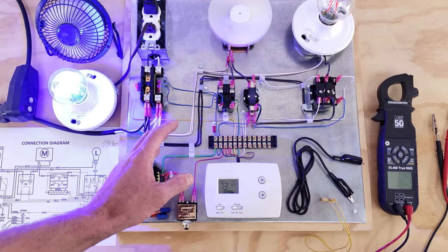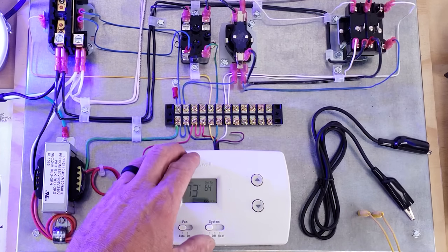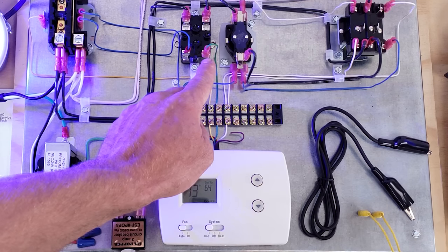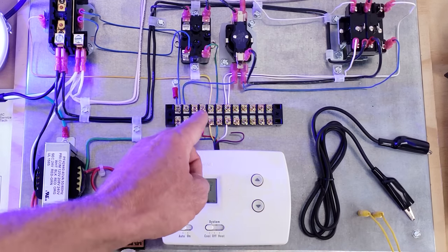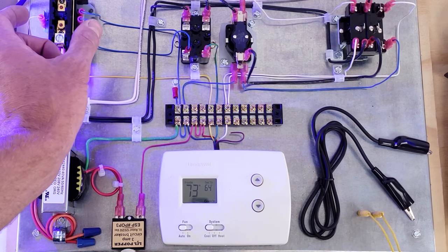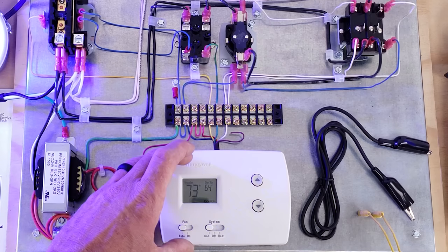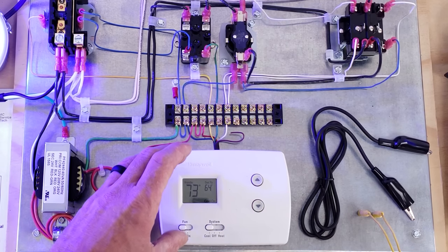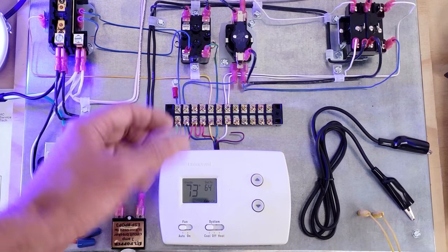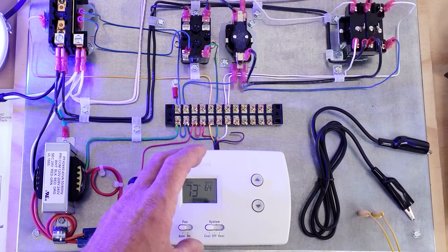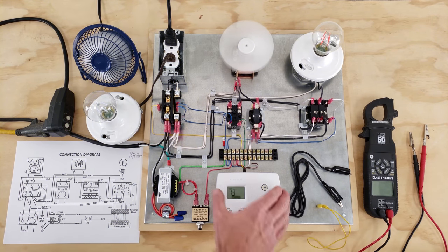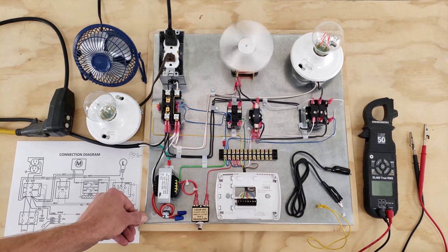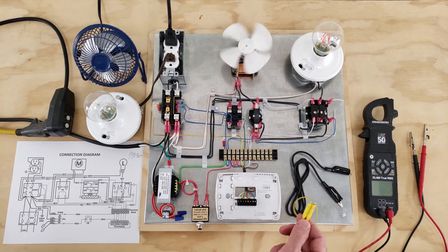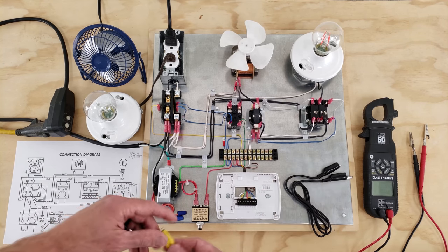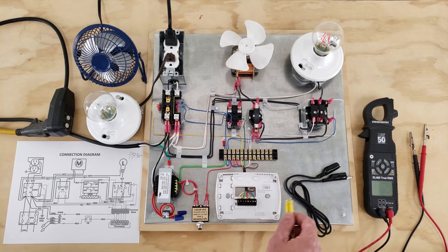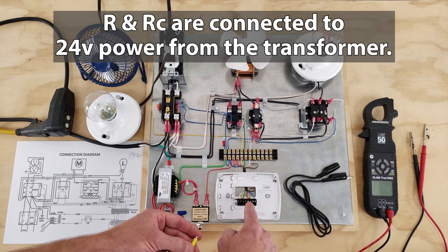Now, what's happening here is that the thermostat is always powering our green fan wire to our fan relay and also our yellow wire to our contactor, which will be outside. So our thermostat is the switching mechanism in any gas furnace and air conditioning system or air handler. This is the switching mechanism, so I want to show you how that works. We'll turn this off right here, and then we're going to remove this faceplate. And we're using our Diversitech mag jumpers right here, or our alligator clips, in order to jump out our thermostat terminals. So right here we can jump out from R to G.